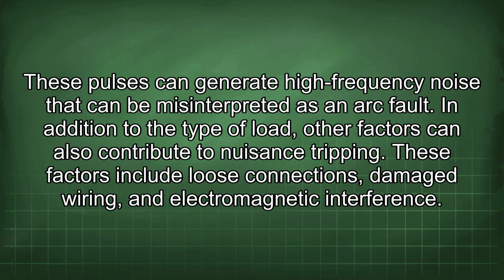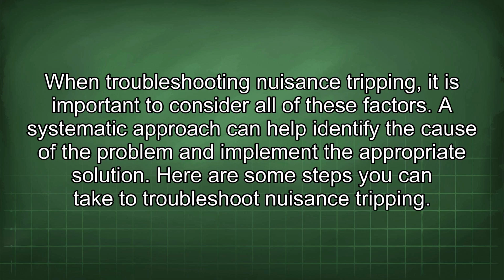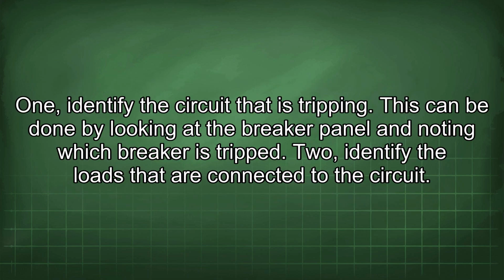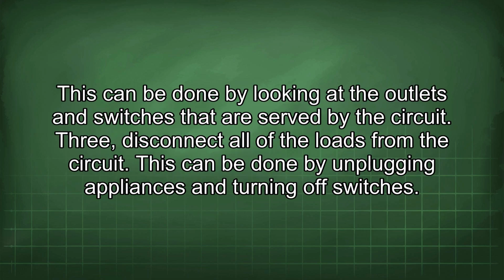In addition to the type of load, other factors can also contribute to nuisance tripping. These factors include loose connections, damaged wiring, and electromagnetic interference. When troubleshooting nuisance tripping, it is important to consider all of these factors. A systematic approach can help identify the cause of the problem and implement the appropriate solution. Here are some steps you can take to troubleshoot nuisance tripping. 1. Identify the circuit that is tripping. This can be done by looking at the breaker panel and noting which breaker is tripped. 2. Identify the loads that are connected to the circuit. This can be done by looking at the outlets and switches that are served by the circuit.